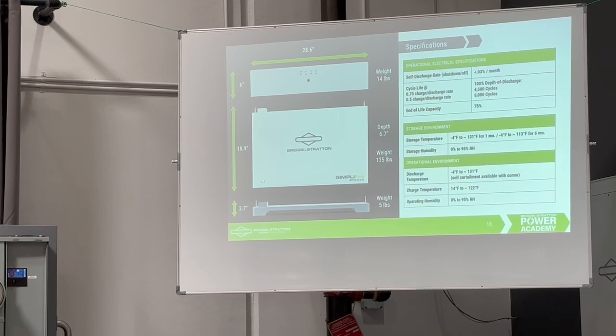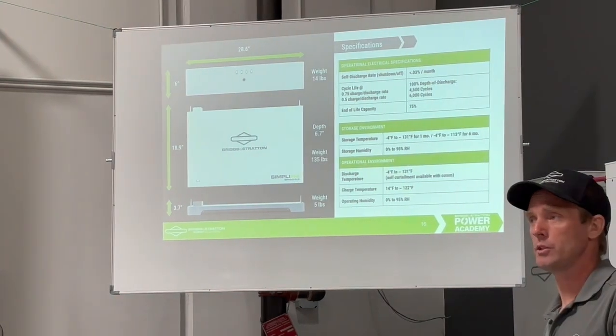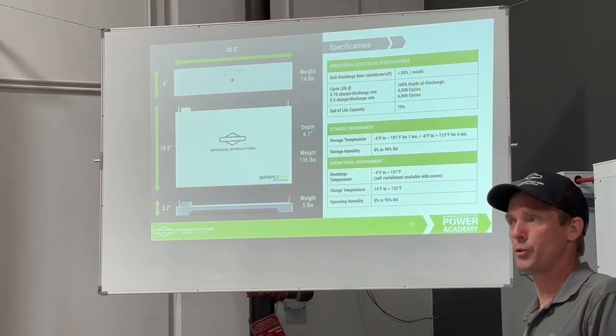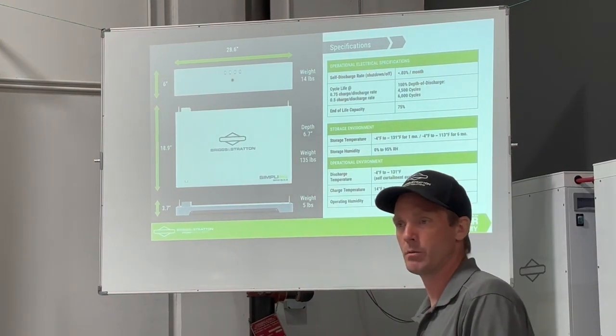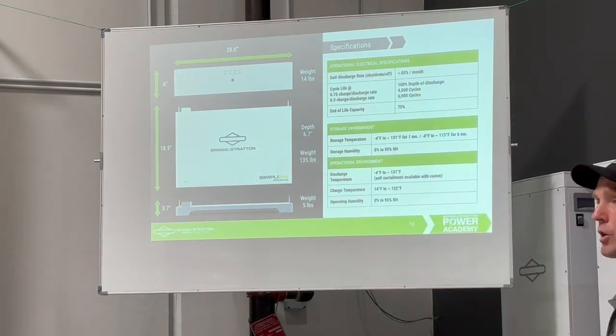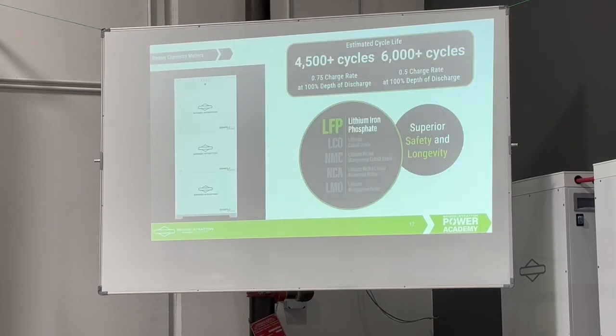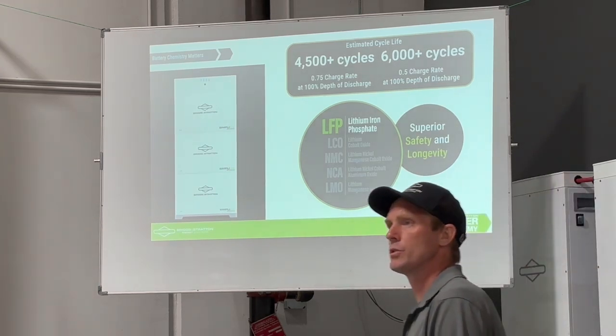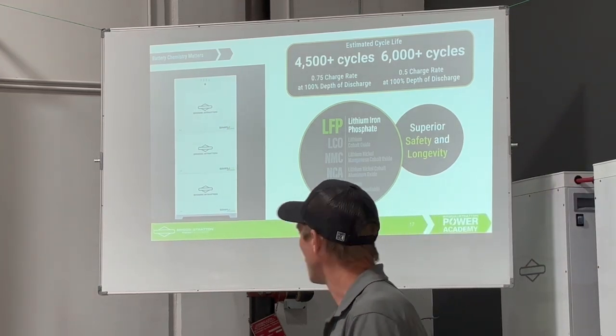And if you've got a generator integrated in your system and you want to charge your battery quickly so you can turn the generator off and save your fuel, that charge rate matters. You've got the generator going, it's cold and it's nighttime, the temperature matters. So those are some of the features to point out about the batteries here. We're looking at 15 to 20 years worth of cycles.